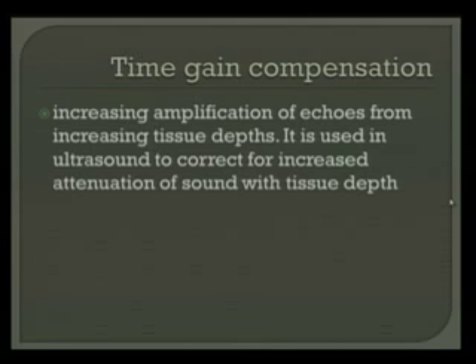Okay, time gain compensation. Increasing amplification of echoes from increasing tissue depths. It is used in ultrasound to correct for increased attenuation of sound with tissue depth. So has anybody seen the TGC on the ultrasound machine? Where is it located? Is it a knob? Good, it's a series of buttons, arranged in an array, like a linear array. And they go from superficial to deep, right? And then you can change them.